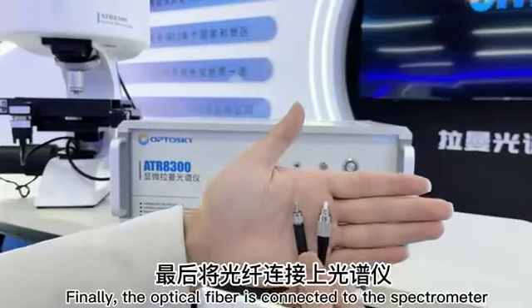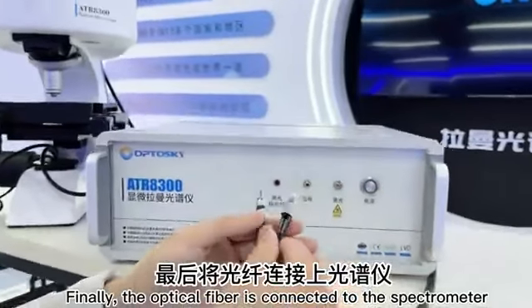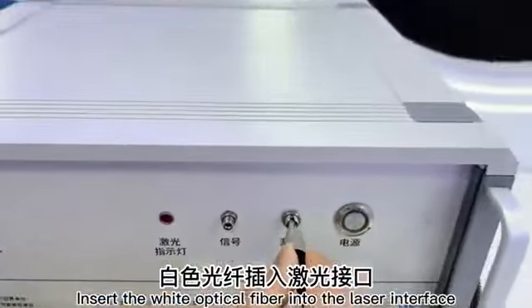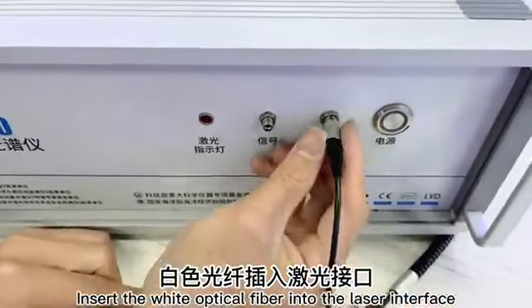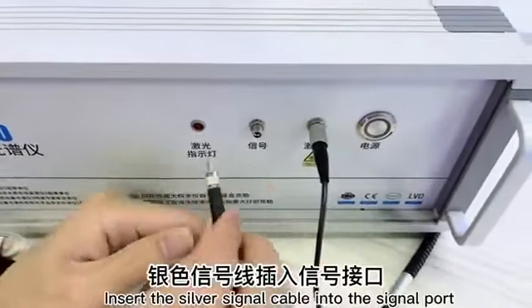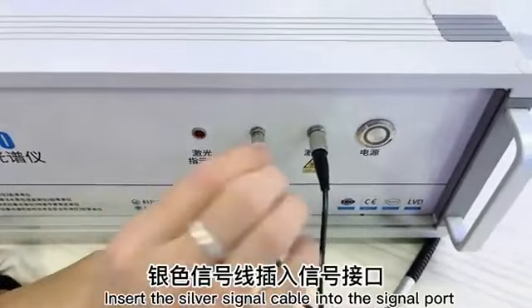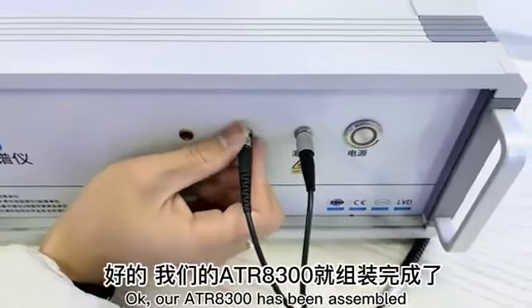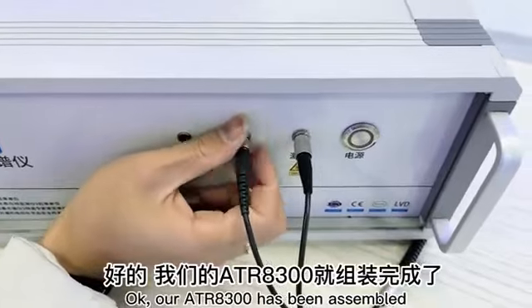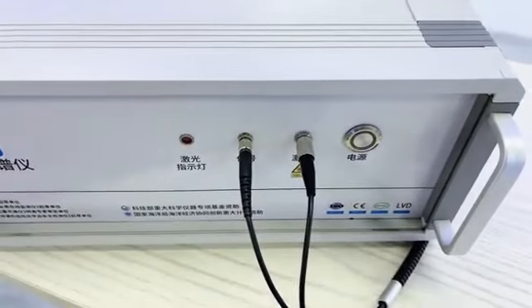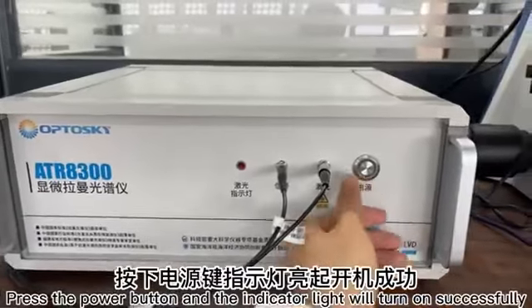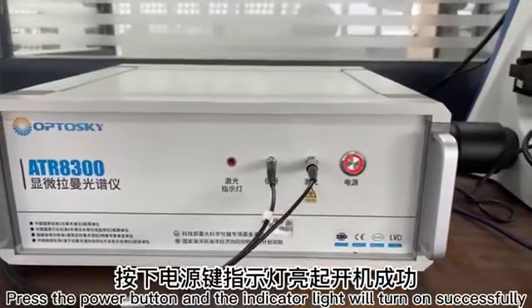Finally, the optical fiber is connected to the spectrometer. Insert the white optical fiber into the laser interface. Tighten the nut. Insert the silver signal cable into the signal port. OK, our ATR8300 has been assembled. Press the power button and the indicator light will turn on successfully.